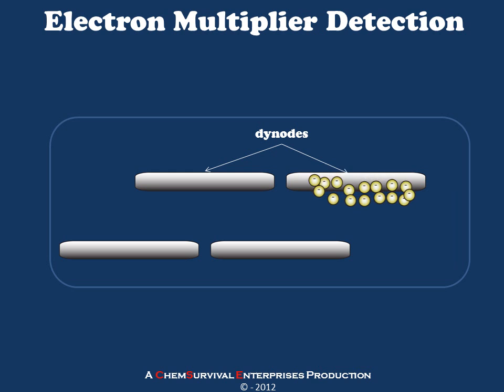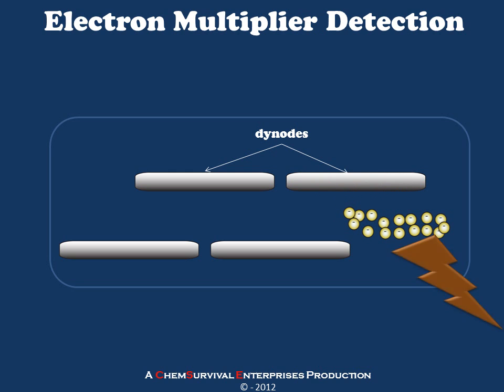A new set of impacts creates even more electrons, and very quickly a measurable amount of current is generated. In our cartoon, we've only created about 20 or so electrons from a single impact, when in fact within the instrument, about a million electrons are generated per impact in a well-tuned electron multiplier. This means it only takes a few impacts to generate enough electrical current for the workstation computer to pick up and read as a signal coming from the detector.